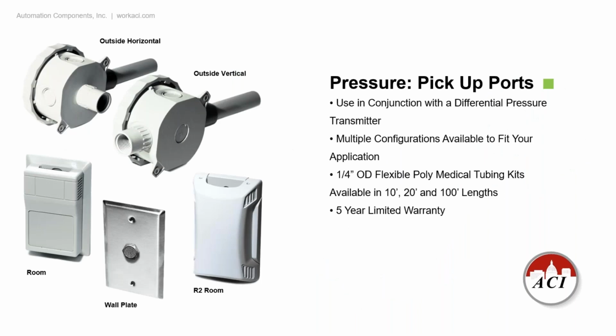Here are the different pickup ports that go along with the pressure sensors for the dry side. You can use them with the DLP, the MLP2s, the DBLs, or the AFSs. It's just an easier, cleaner way to dress up the wall plates or the room enclosures. It's a little pressure port behind the enclosure itself, versus running the tubing into a drop ceiling and simply putting it into the top of the ceiling. You can actually put these on the wall. Now, if you're doing differential air, so the outdoor versus the indoor pressure, you can use our outdoor horizontal or outside vertical mounting feature product as well. Again, we have a 5-year warranty on all these devices. We do sell the poly tubing as well, up to 100 feet in length.